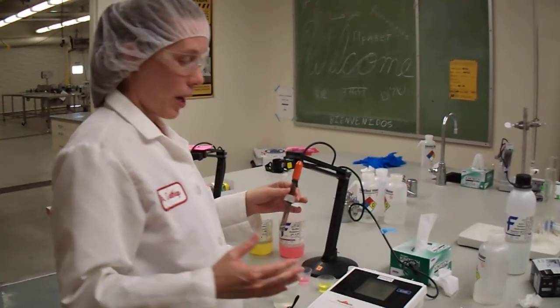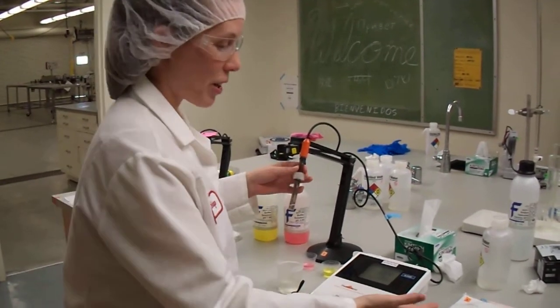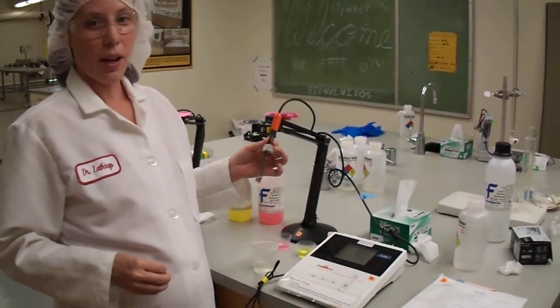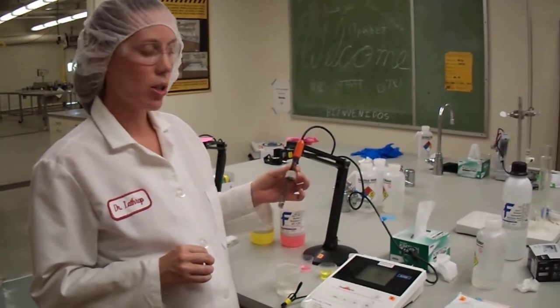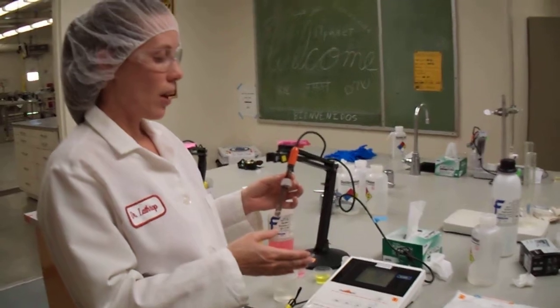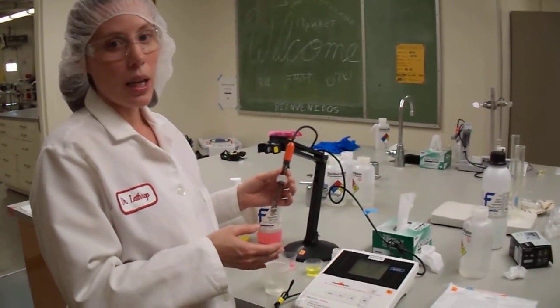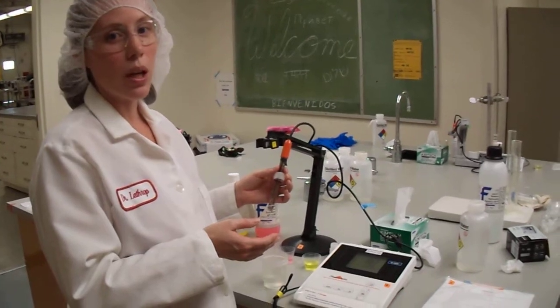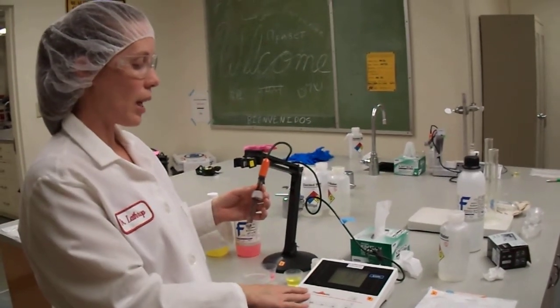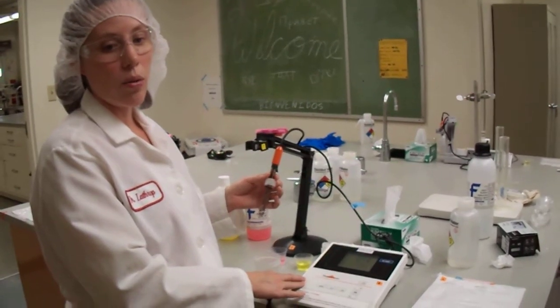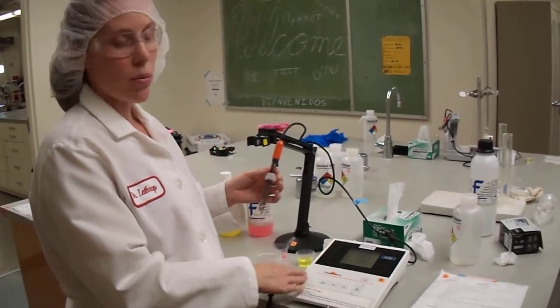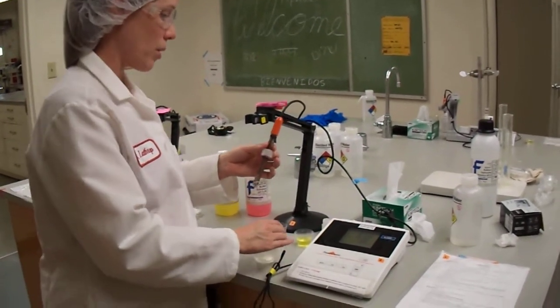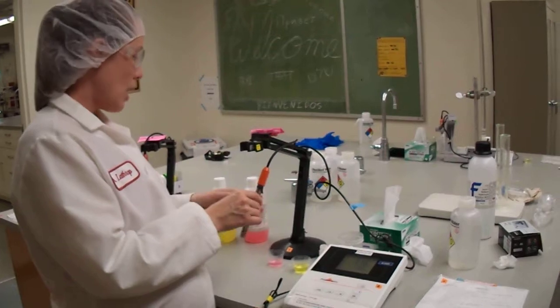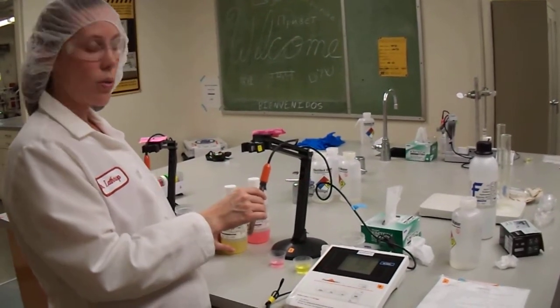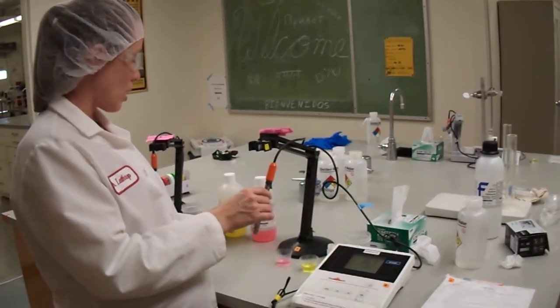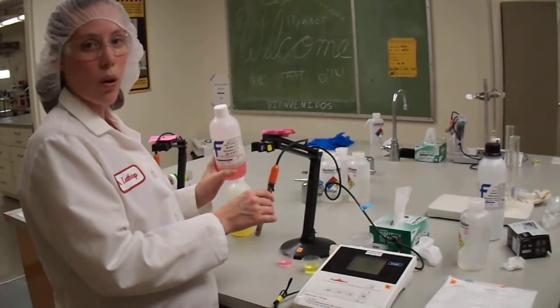So since I've never calibrated this pH meter before, and since the directions are here, I'm going to have a friend come and help guide me through the calibration process. We are going to first calibrate the piece of equipment before taking a measurement. Calibration ensures that the piece of equipment is working properly, and if this was not calibrated properly, we would know that the equipment is malfunctioning, and taking a measurement would not be all that useful because it's broken. We're going to do a 2-point calibration, and we have some buffer solutions here that we're going to be using. We'll use a 7, which is yellow, and then the pH 4, which is pink.